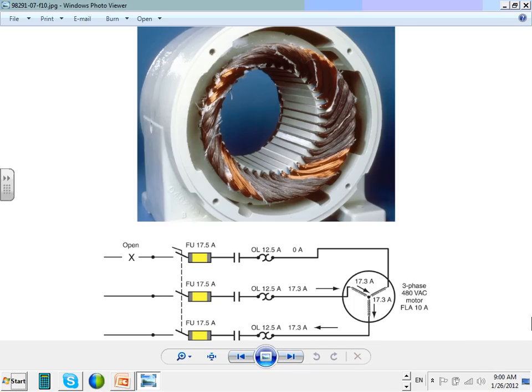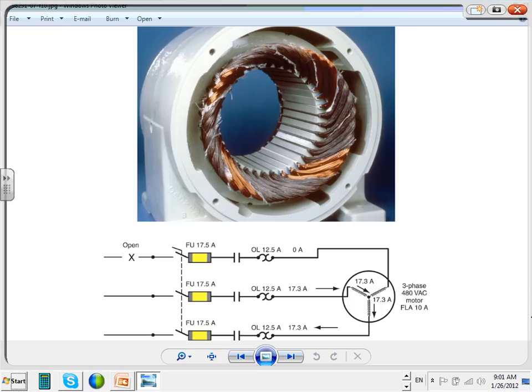Look at this situation. Now we talk about single phasing. If we have a single phasing situation, this is a 3-phase motor, and I lost phase A because a storm took down the phase A on the transmission line or something happened. I lost phase A. What happens if you lose phase A on a 3-phase motor, guys? The current here will be 0. There is no voltage on that line. Then these, instead of being 10, 10, 10, to compensate for it, go up to 17, 17, 17, right? On each, because it has to compensate for the loss of the 10 amps from the other line.